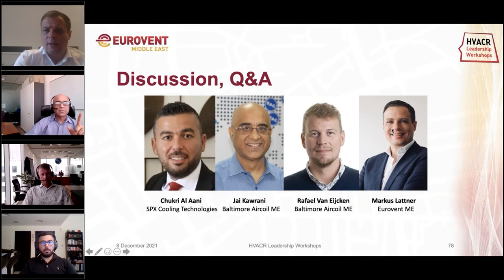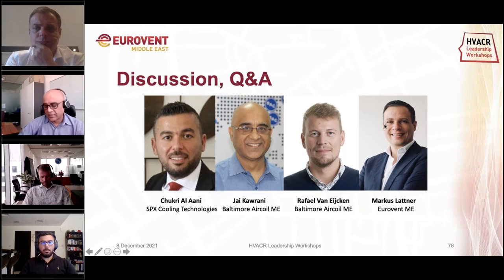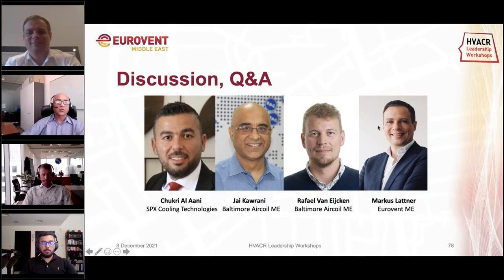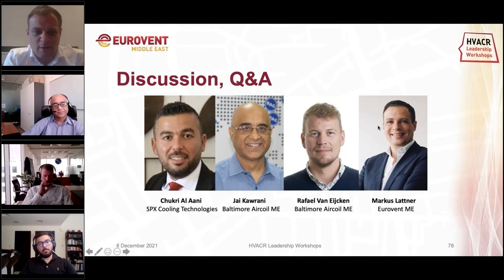Just one addition to what you mentioned. I have seen many people, what they do is some manufacturers who are not certified can still be a member of Eurovent or member of CTI. So what they mention on their cooling tower nameplates is member of Eurovent, member of CTI. But those are not certified cooling towers, because certification would mean that the thermal performance of the cooling tower is as per, let's say, the CTI 201 standard or whatever the standard is. Member of CTI or member of Eurovent doesn't mean that the product is certified for its thermal performance. That's what I wanted to add.